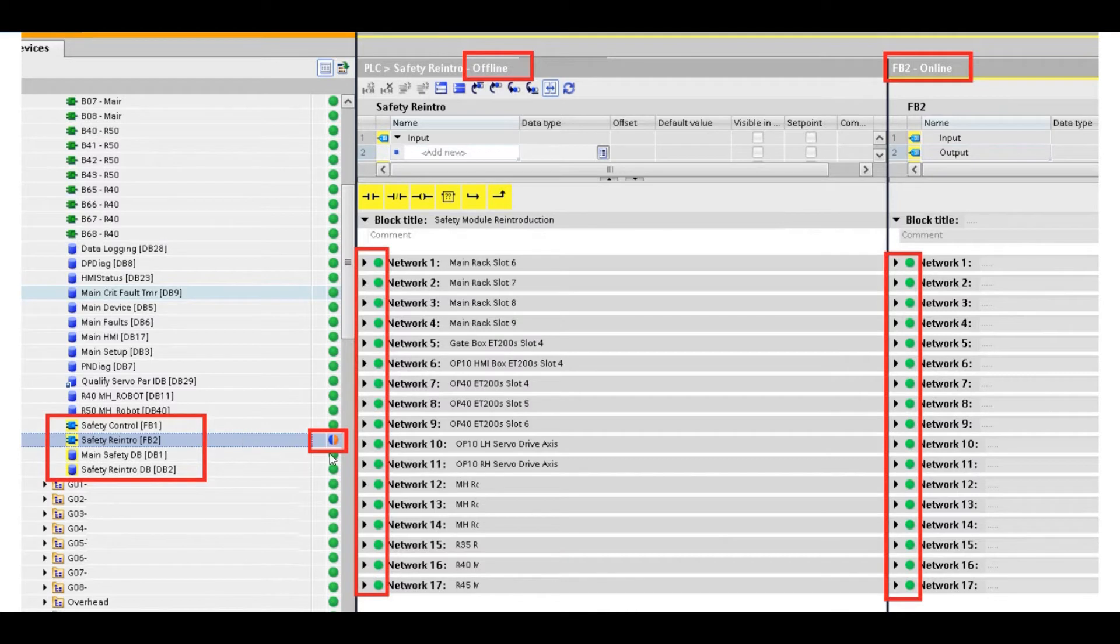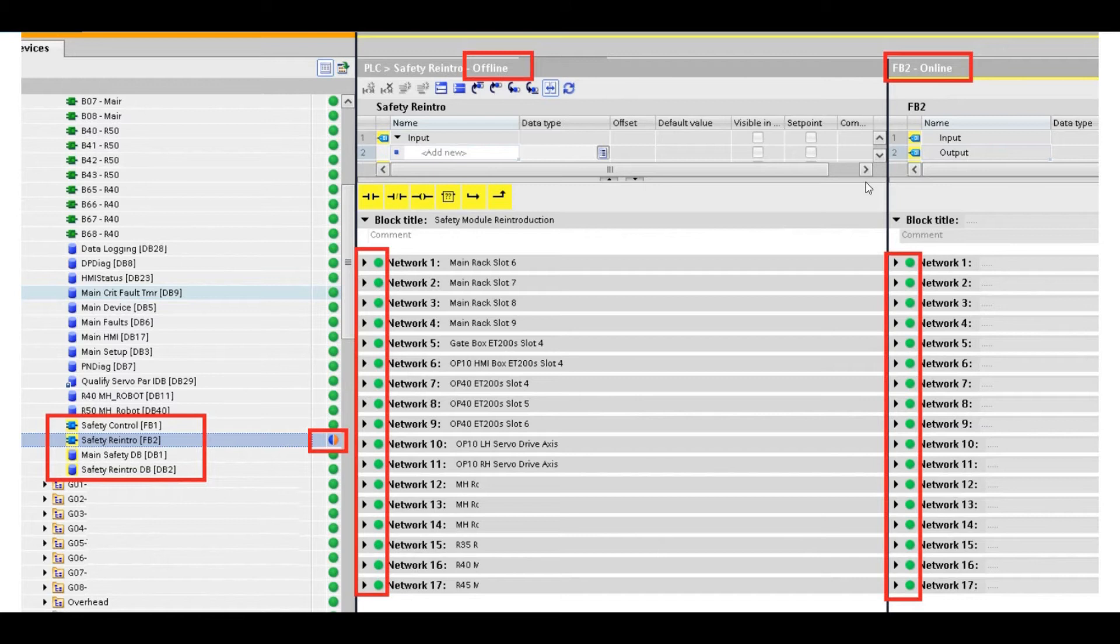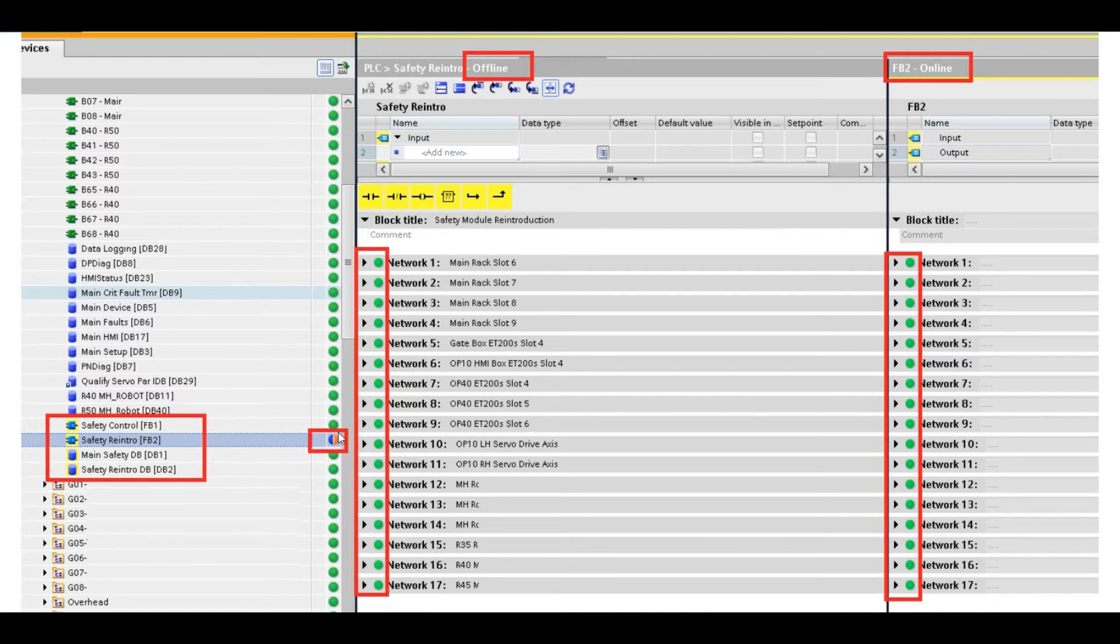So it's really odd. The program still shows the difference. The safety logic, offline and online, they are all the same. But this icon always shows doesn't match. That is a very typical issue for the Siemens safety program.